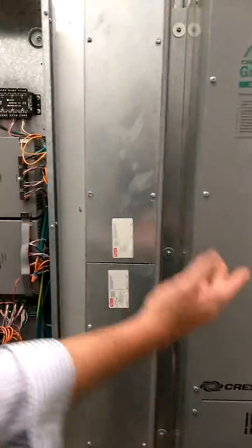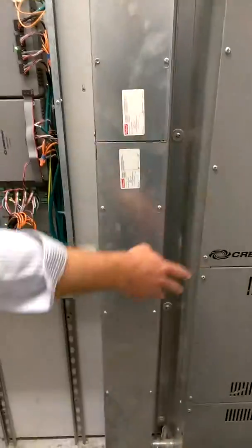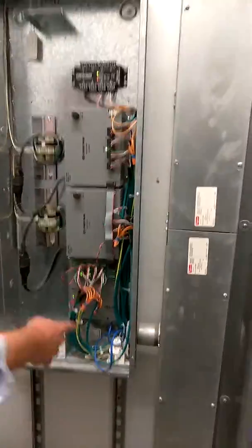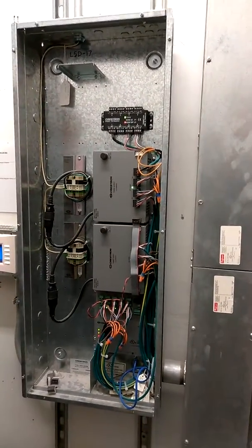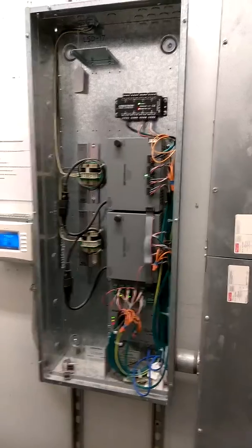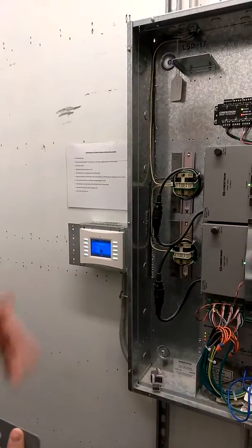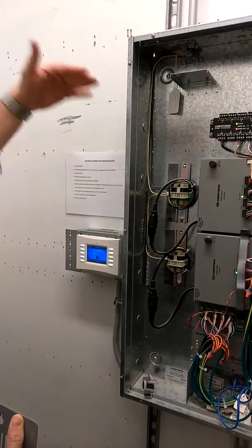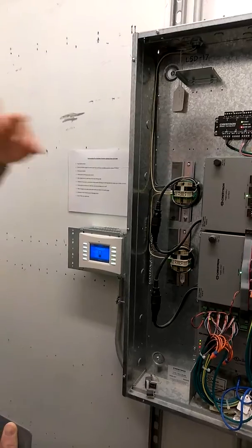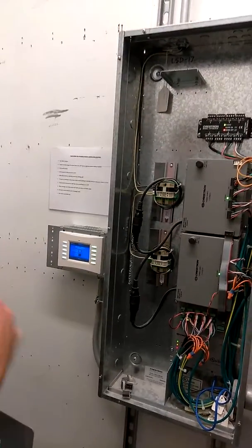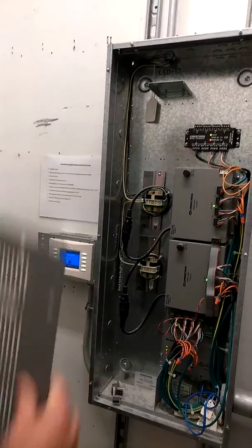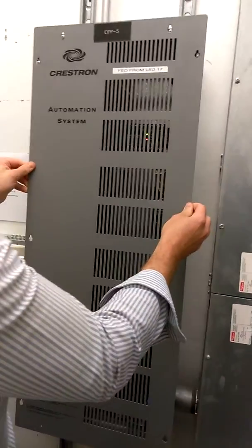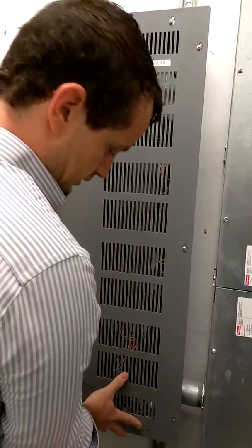All these cabinets are high voltage. Those are your dimmers and switches, and those units talk over the same Cresnet wire. So there's a wire going from here to there that all that communication is happening over. All right. So again, the important part is if you have something that's going to go on late into the night, you can come in and either set that scheduled event to happen later. Like if they're going to be here until 10, you could say, hey, turn the lights off at 11 p.m. Or if they're going to work all night, you can just disable the scheduled event from happening on that floor. And that should get you by.